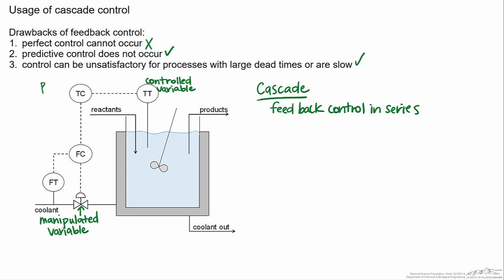So the temperature controller is represented as the primary controller. The primary controller in a cascade control scheme will always be the controller that corresponds to the controlled variable, in this case the reactor temperature. And the flow controller is the secondary controller, primary, secondary. There can be more than two layers of cascade control, so it can be ternary, quaternary, etcetera. Whatever is lowest in the hierarchy is the one that will directly control the valve.